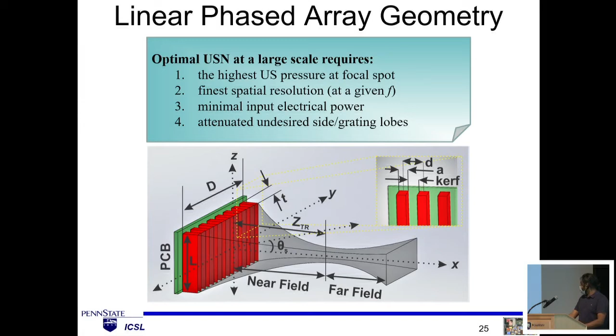But for the design, we need to consider a few things. For neuromodulation, it's very important to have enough pressure and also a small focal volume. And also, we want to minimize the electrical input power. As well, we want to attenuate undesired stimulation. So we can achieve these things if we consider the design parameters and design in a systematic way. For example, for a linear phased array, some important parameters are the inter-element spacing, which is denoted as d, the element width, which is A, and also the aperture, which is capital D here. So these are some important parameters to consider.